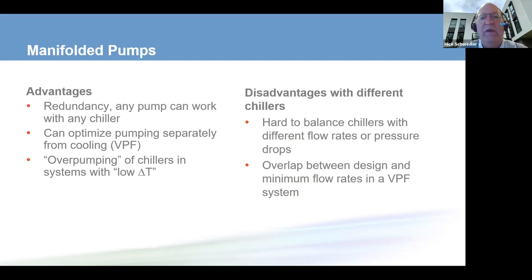The next part is we can now optimize our pumping separately from optimizing our cooling, particularly in a variable primary flow system. If we have four chillers, we might have two or three pumps. They don't have to be sized together. That can help us from a space standpoint in the chilled water plant, but particularly an efficiency standpoint. And the third thing we'll talk about is over pumping of the chillers if the system has experienced what's called low delta T syndrome.